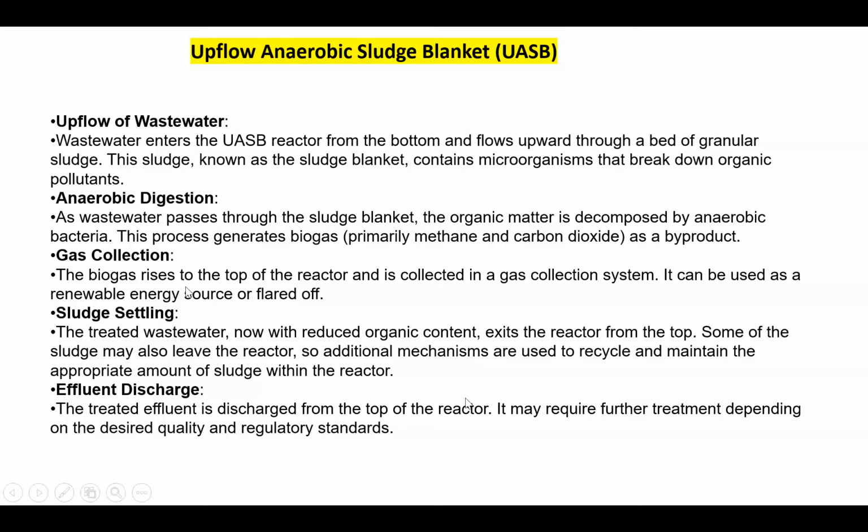Then the biogas rises to the top of the reactor and is collected in a gas collection system. Then sludge settling also happens here. The treated wastewater, now with reduced organic content, exits the reactor from the top. Some of the sludge may also leave the reactor, so there are additional mechanisms, like recycling.